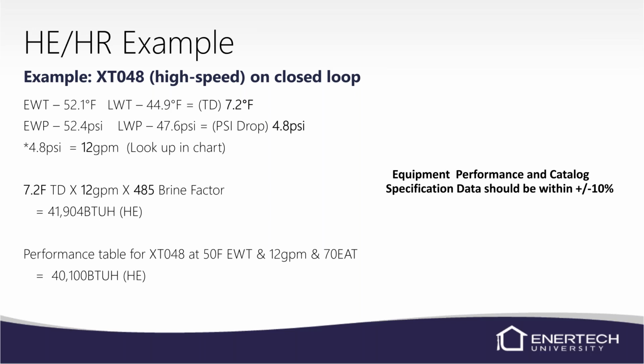Now we just run the math. So we've got our temperature difference of 7.2 times our GPM of 12 times our brine factor. And we've got a closed loop, so we're assuming that you've got antifreeze in there. So multiply that times your 485. That gives us 41,904 BTUs. That's really just a number. I mean, you can say, yeah, on a 4-ton unit, that sounds like it might be all right. But we have to look at the manual.